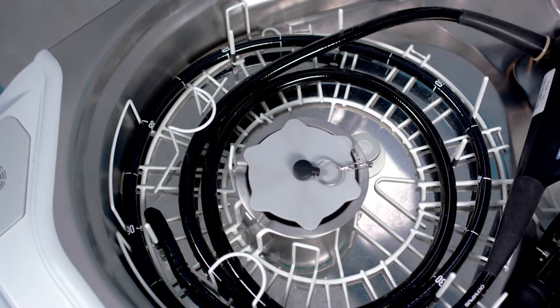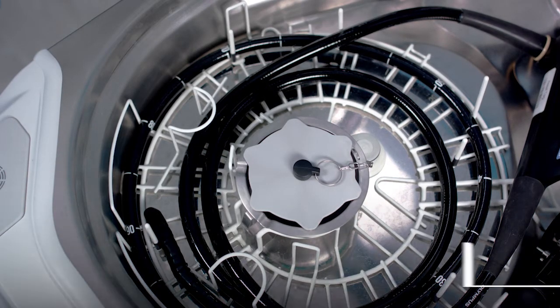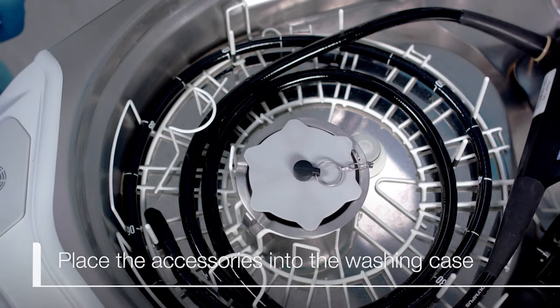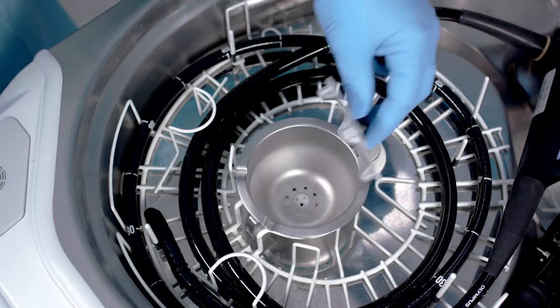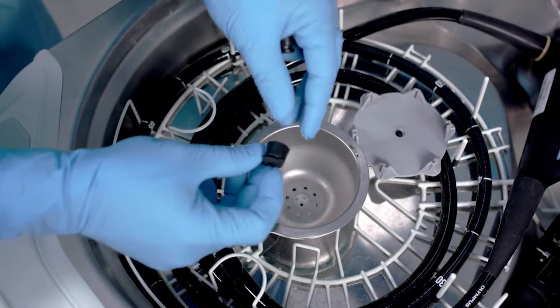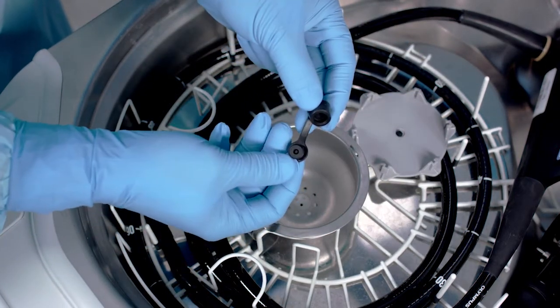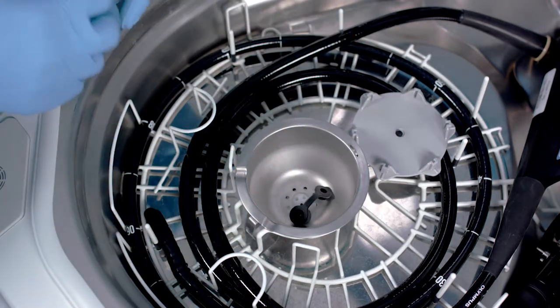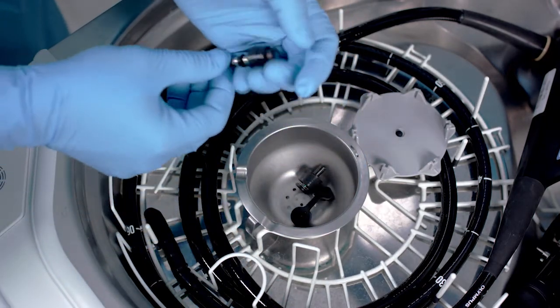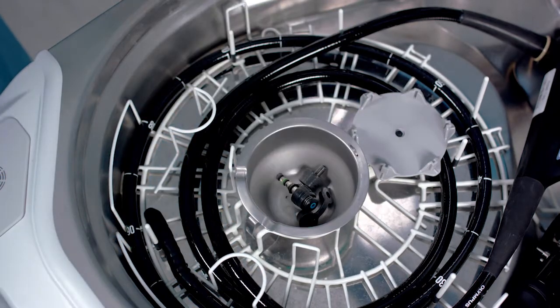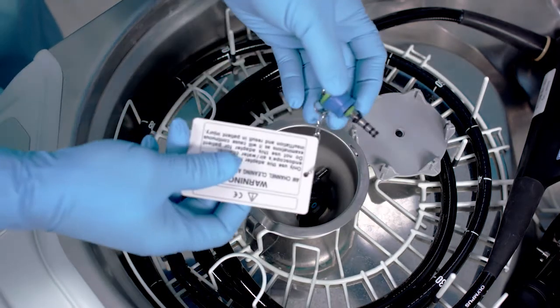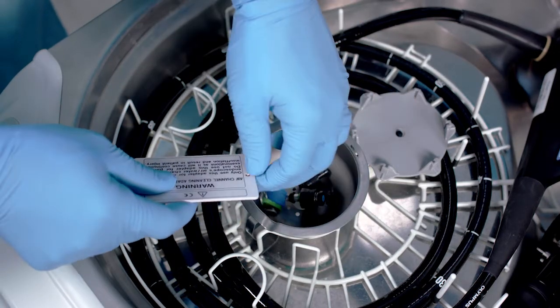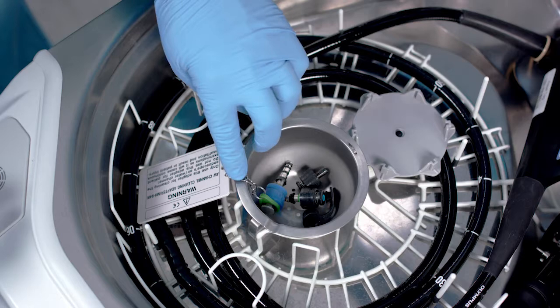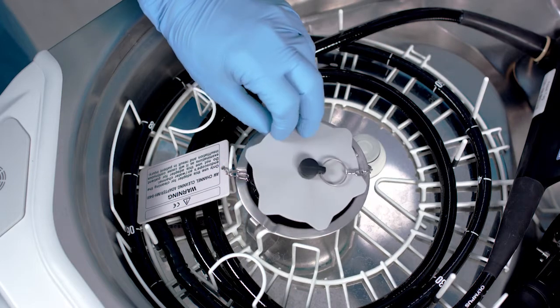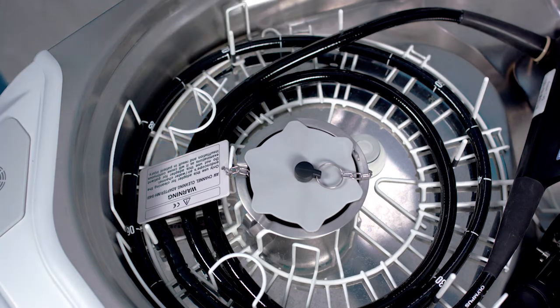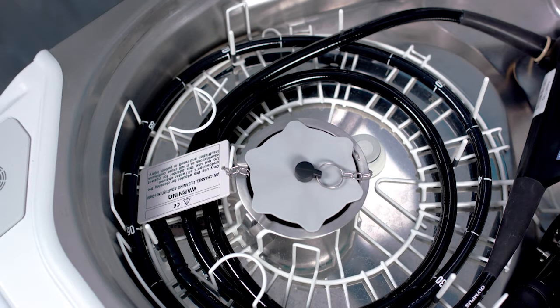Now that the endoscope is loaded into the OER-Elite basin, it's time to place the accessories into the washing case. First, remove the washing case top and place the biopsy valve in the case, followed by the other accessories. Make sure to open the biopsy valve. Disassemble the accessories when warranted. Next, set the air-water channel cleaning adapters in the washing case. Ensure that the indicator tag is draped outside of the case. Finally, close the cover of the washing case so that the chains from the AW channel cleaning adapter are not caught in the washing case lid.